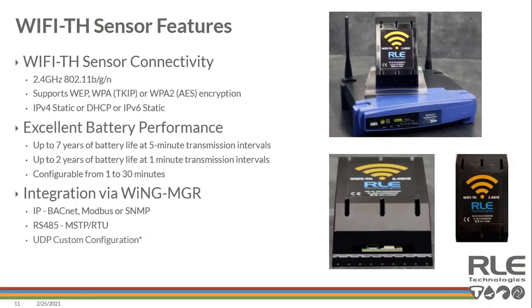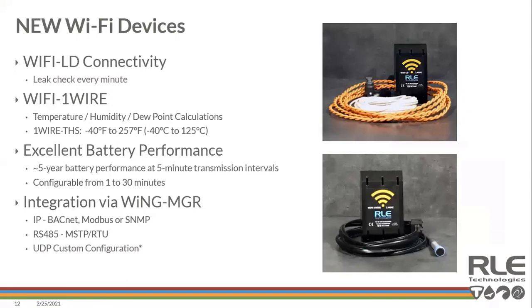And then there are some benefits to integrating with Wing Manager. You can use a BMS or packet dissector to handle all the data processing yourself. Our packet information is available, but you can also use the Wing Manager to integrate with BACnet, Modbus, SNMP over an IP network. There's also RS-485 for BACnet and Modbus, and then our BACnet IP. You can also use a custom UDP configuration, which might be useful in some situations.